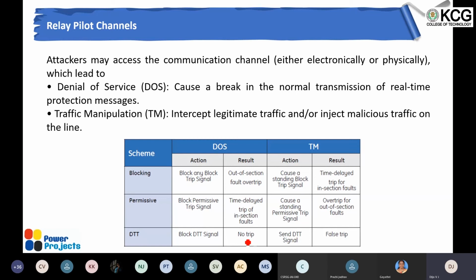And the other one is traffic manipulation. The intruder who gets into the communication network sends a false signal back to the other end. When the signal is received at the other end, it issues a trip command. So it's a nuisance tripping: no fault, but the attacker was able to send a signal to the remote end, and then it gives a false trip. It's a similar case for other schemes also, but since I haven't discussed the other schemes in detail, I'm not talking about that, but this is how it is.